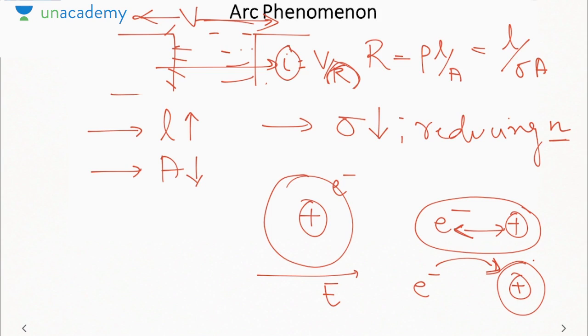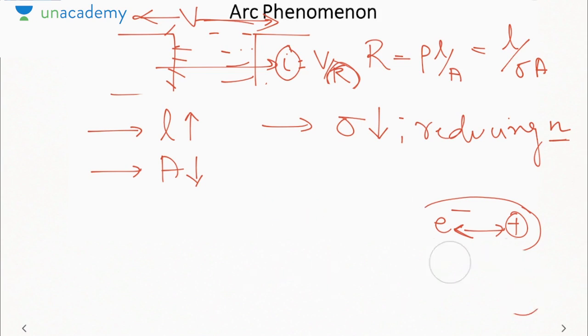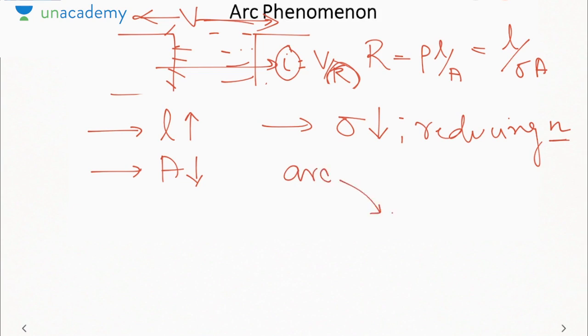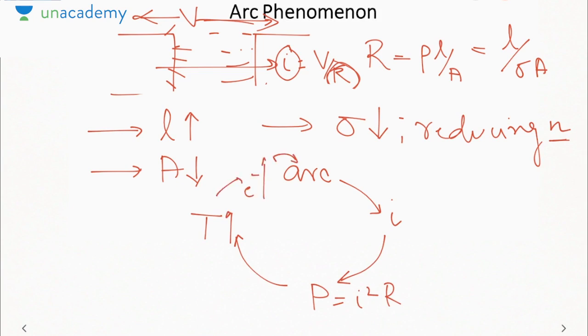Now, why is an arc so dangerous? Why do I need a special method to extinct the arc? This is due to the fact that an arc has a self-sustaining nature. That means an arc will not extinct by itself. It will continue to exist. Why? Because as the arc is formed, current will be flowing, due to which losses, equal to I square R, will be there, due to which temperature will increase, due to which the number of electrons will increase, due to which the arc will be sustained.